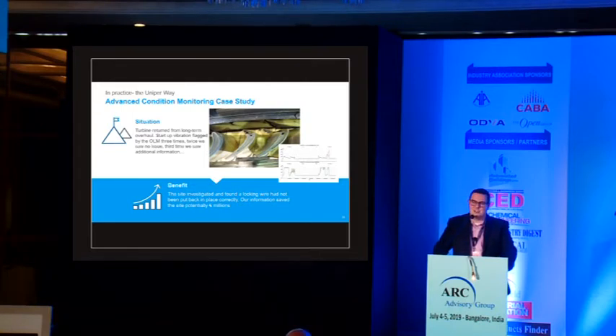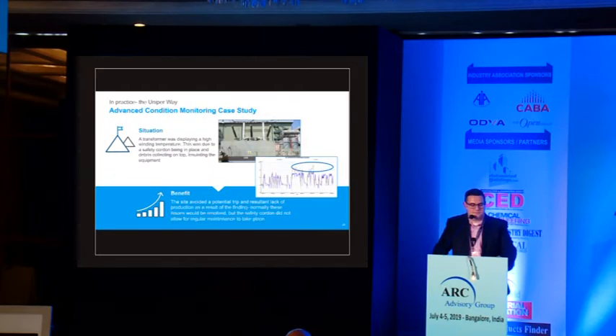So providing that additional information and decision support allowed the site to make a better decision than if they had just had vibration monitoring information. Another example is where a transformer was displaying a high winding temperature.